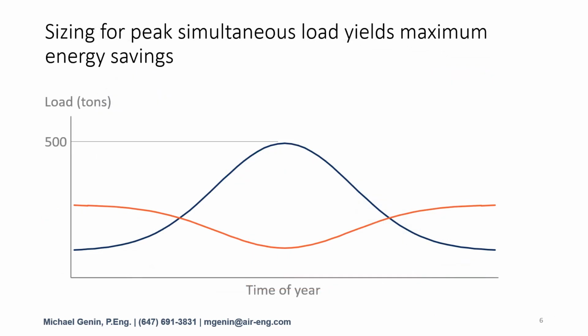No building has a perfect simultaneous load. To demonstrate this, I've drawn this theoretical heating and cooling load profile. The cooling load is in blue, with the peak cooling near the center of the graph representing 500 tons. And the heating load is shown as red, with the peak being at the ends of the graph representing wintertime. As you can see, these loads are not the same, but there is always at least some kind of simultaneous load.